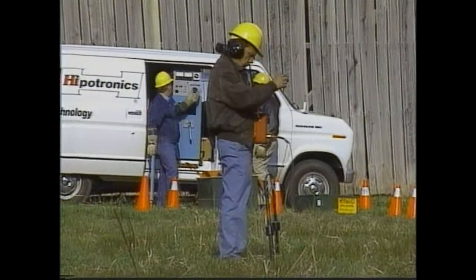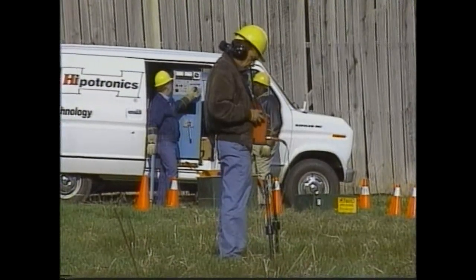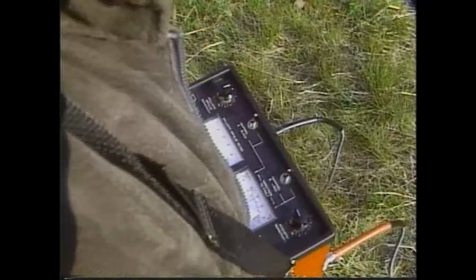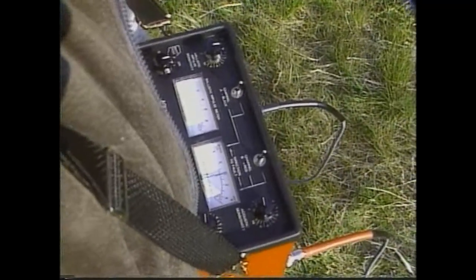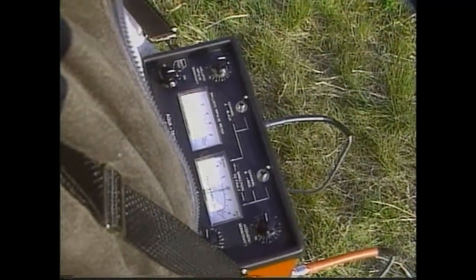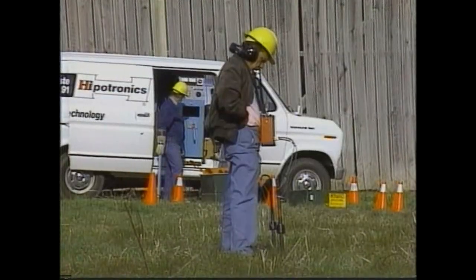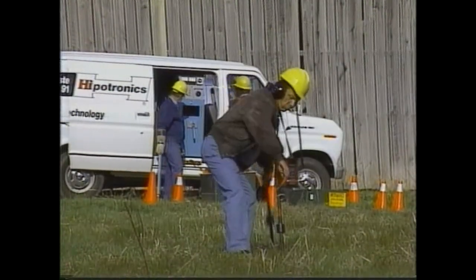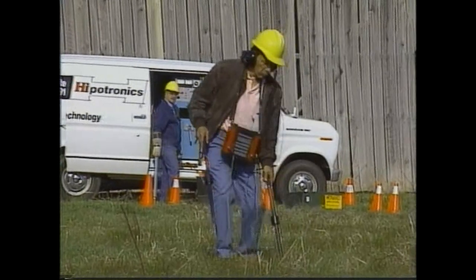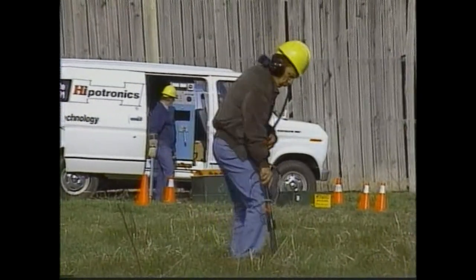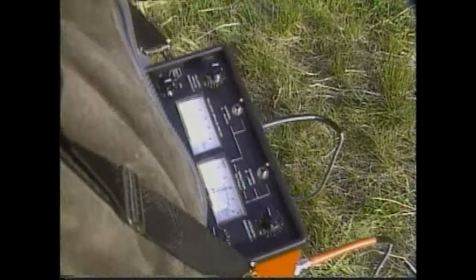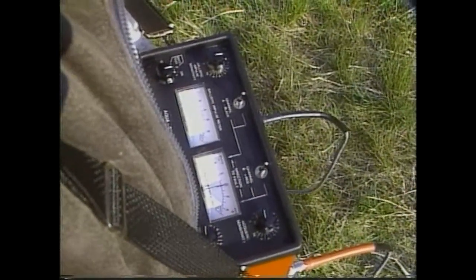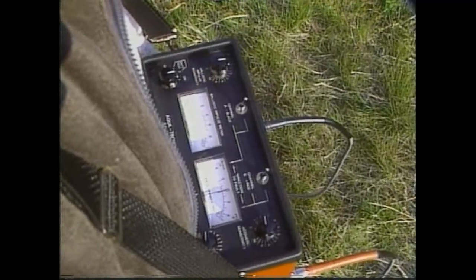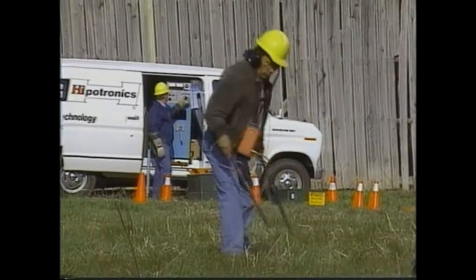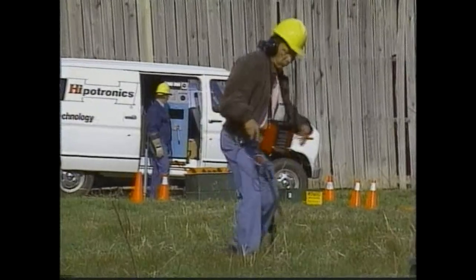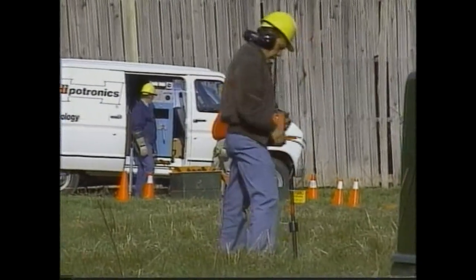I set the headphones to stereo and I adjust the logic trip sensitivity control up until the logic trip meter trips. Here the meter is tripping to my right, which means the right probe is picking up the sound of the thump before the left probe senses it. I move about 10 feet down the route of the cable and take another stereo reading. My logic trip meter is telling me the fault is still to my right. This time when I move another 10 feet down the route of the cable, my logic trip meter has reversed direction and is tripping toward my left hand.